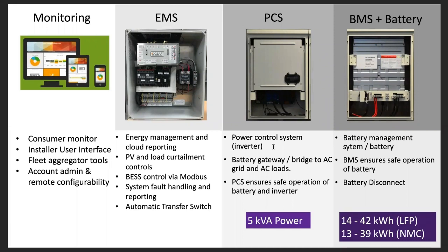It's rated at 5 kVA or 5 kW in power. So while grid tied, it will only charge or discharge up to 5 kW, but in off-grid mode does have some surge capability in discharging. This is again listed on the product resources. You can find this information on the data sheet online. It'll surge up to 120% of nameplate or 25 amps or 6 kW for up to 30 minutes, and will surge up to 170% of nameplate or 8.5 kW or 35 amps for up to 5 seconds.